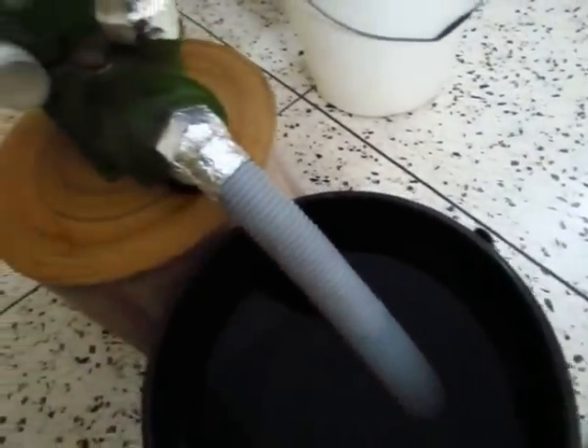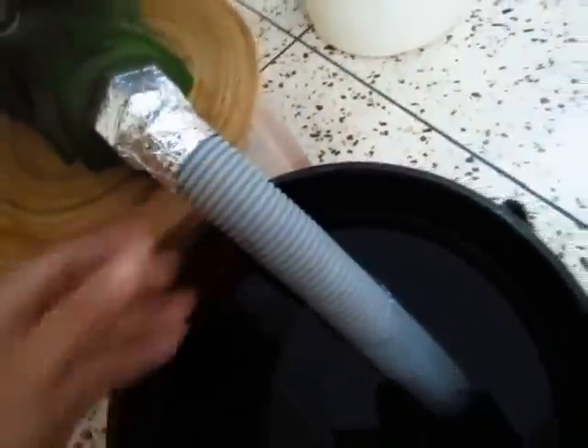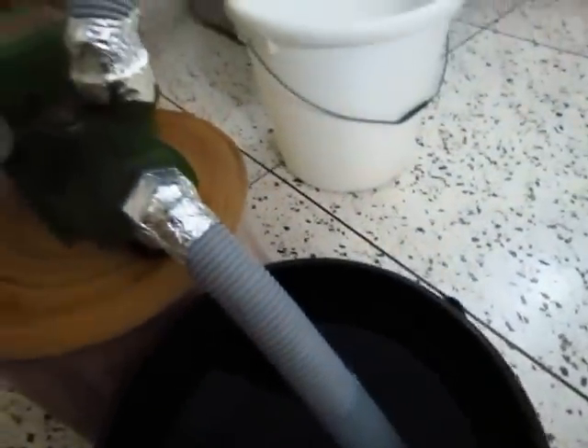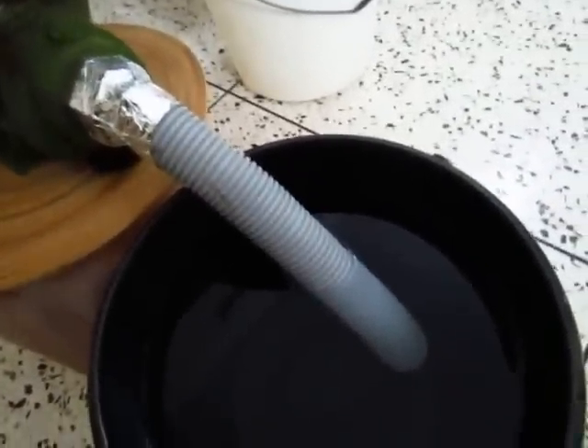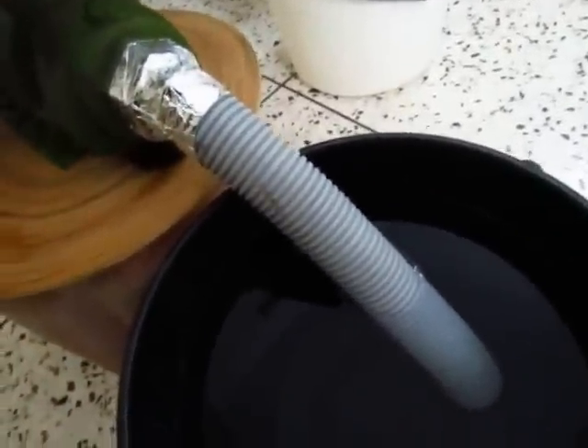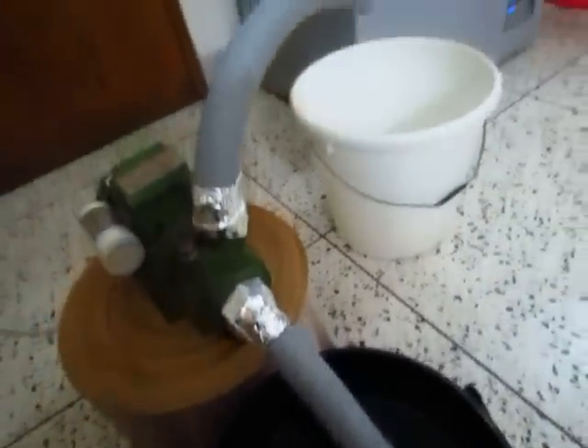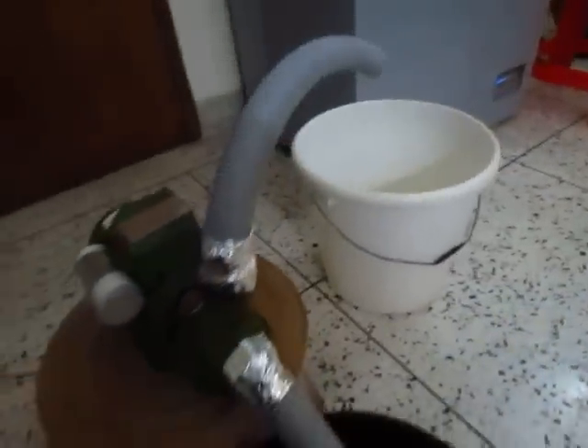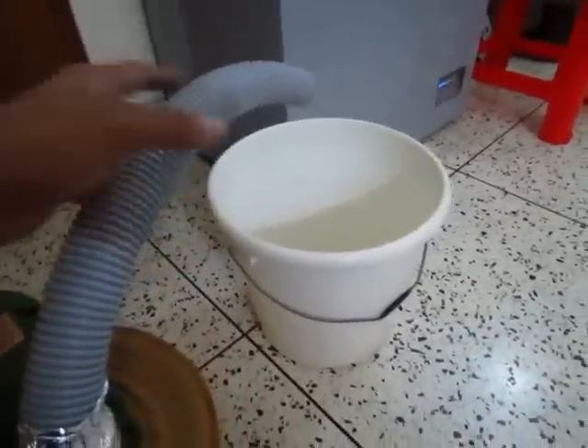What's happening in this scenario is this pipe over here is filled with air. This is a typical situation that would happen if you unplug the pipe, leave it unused for a while, or if you're trying to draw water out of a well or a pit — obviously this pipe would have air in it. Let me just turn it on and show you what's happening — you'll see that nothing comes out of the discharge pipe.